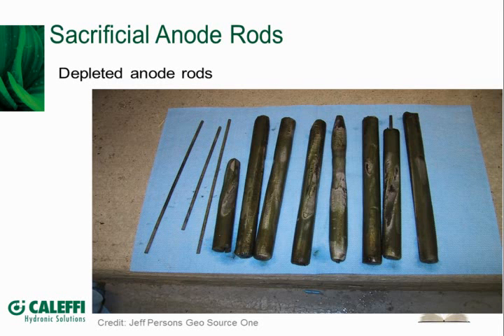I remember too, Jeff, when indirects became popular in the market, people said, well, yeah, you can put a much smaller indirect than you would have with a gas-fired water heater because you've got the horsepower of your boiler and they recover quick, and you're going to have all this hot water and never run out. Well, that wasn't necessarily the case with homes with big dump loads and stuff. So what did they start doing? They started cranking them up, and so they'd crank those indirect water heaters up to 140, maybe 160 degrees or even hotter, and put a thermostatic mixing valve on them.